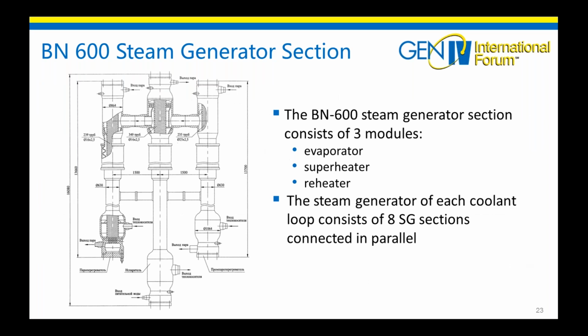This figure shows the BN-600 steam generator section that consists of 3 modules. Its evaporator is in the center, the superheater is on the left, and the reheater is on the right. The steam generator of each coolant loop consists of 8 steam generator sections connected in parallel.